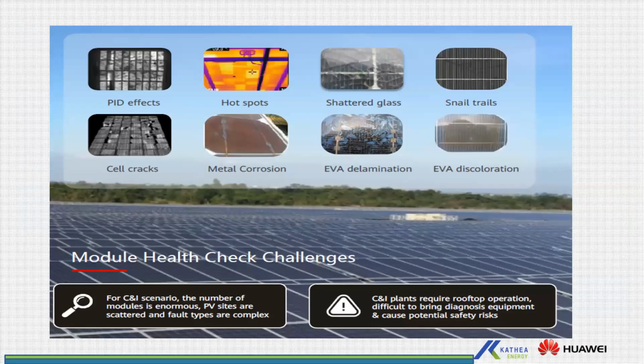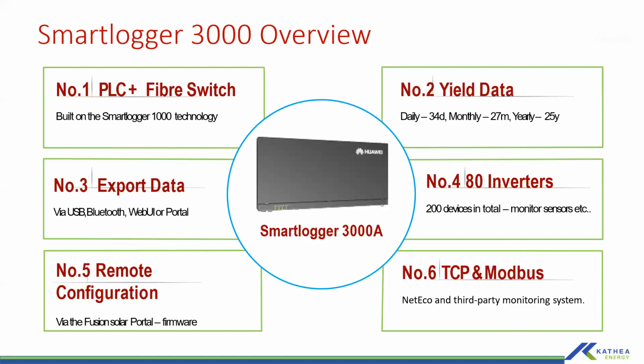And then our major component in the C&I is the Smart Logger 3000, which is basically the communication device. It's the one which interfaces the inverters with the management system, as well as controlling inverters, giving set points for export control and all that. So the logger can support up to 80 inverters. However, the smart logger has an expansion module. If you have more than 80 inverters, you can install an expansion module, which can take your devices up to 200. So basically the expansion module is more inputs to add more devices.